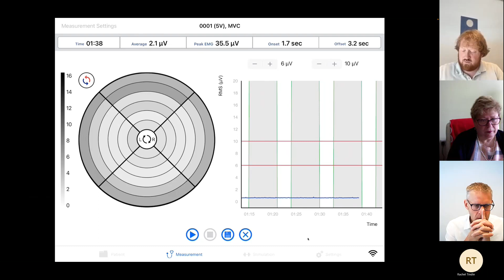Now, if I stop the measurement by pressing the stop button here, I see the average EMG signals I recorded during the measurement. They're also listed here. And I have the option to either save the measurement or throw it away. Now, if it's saved, it goes directly into the history tab you saw earlier. If I throw it away, I always get a pop-up that says, are you sure? Because there's measurement data available. Do you want to save it? Well, in this case, I do want to save it, so I press yes.